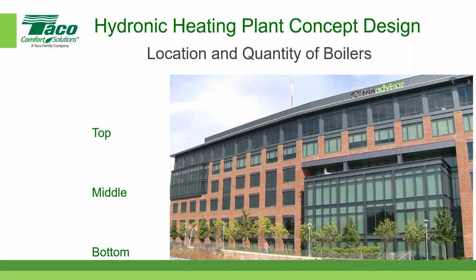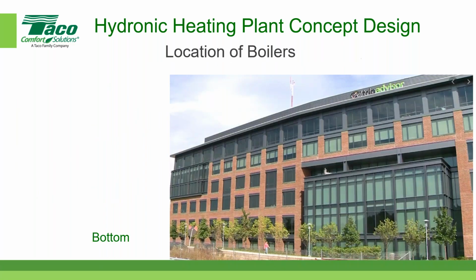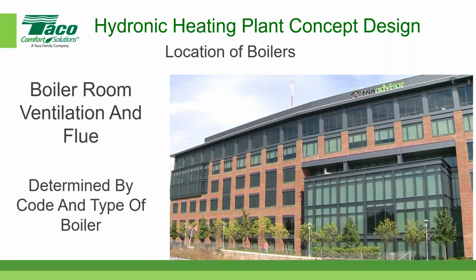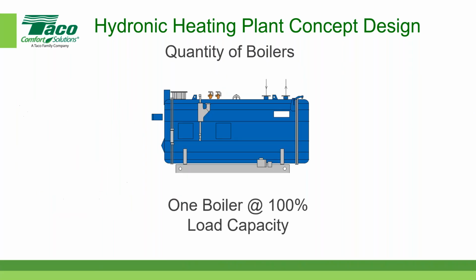But I have designed buildings in the past where we have put the heating plant in a penthouse. So you can have it almost any way you want. I personally prefer, here it goes, to put it at the bottom of the building. So I would put a check mark. That's where my preference is. The other thing to consider is the boiler room ventilation and flue, determined by code and type of boiler. So again, we keep going back to the code issues.